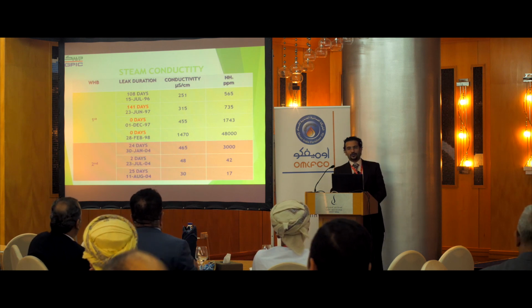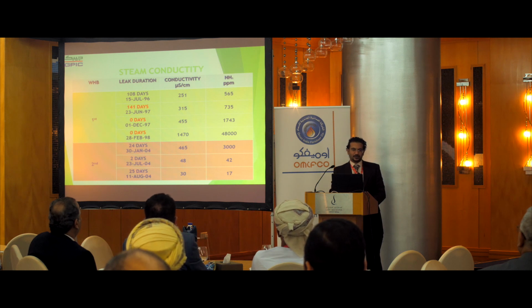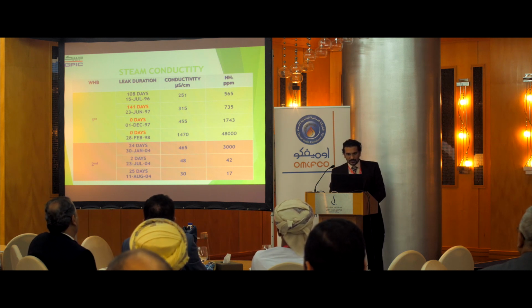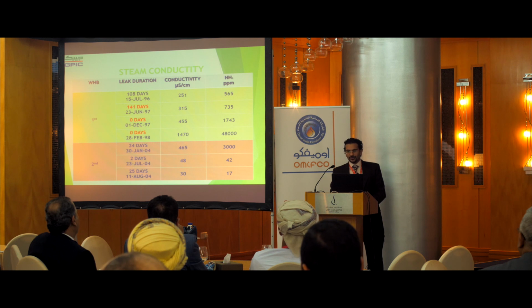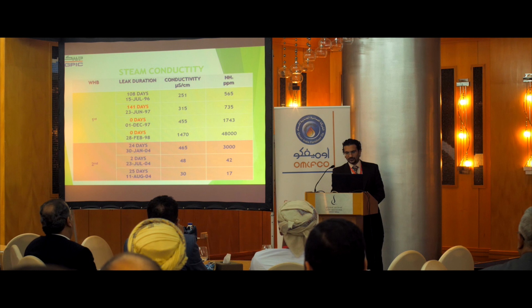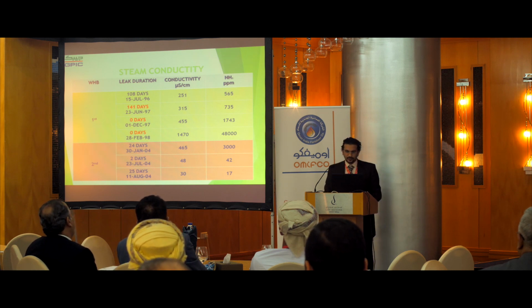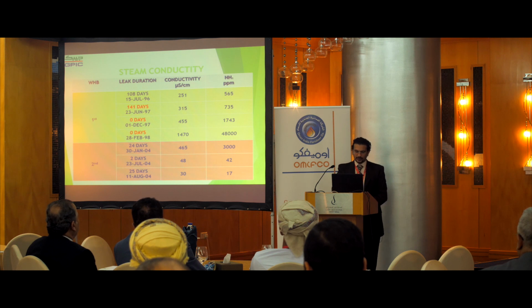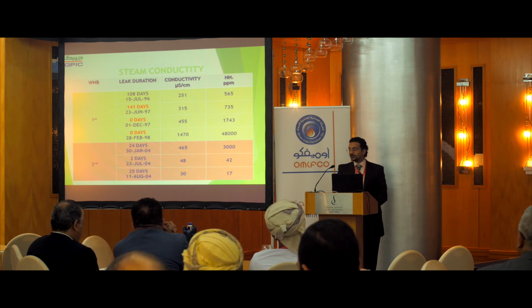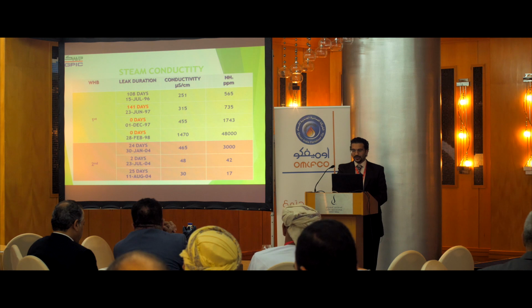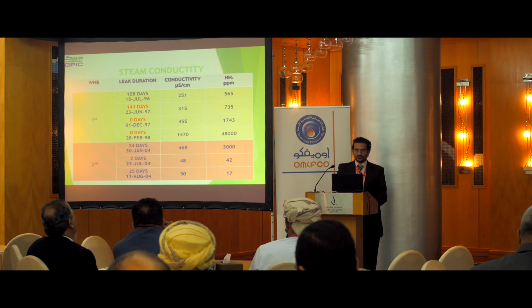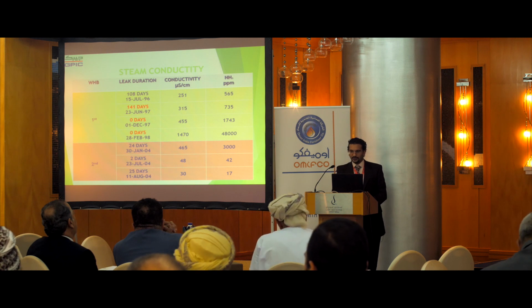This is just a record of the steam conductivity when we got the leaks of the waste heat boiler. So our Bellelli boiler, the leak duration was 108 days. Our conductivity was 251, and ammonia went 565. By the end, on 28 February 98, conductivity reached 1470, with 48,000 ppm ammonia. And our second waste heat boiler, our first leak, 465 microsiemens per centimeter, and then ammonia 3,000. And finally, when we replaced it, after taking our measures, conductivity was 30 and ammonia ppm was 17.